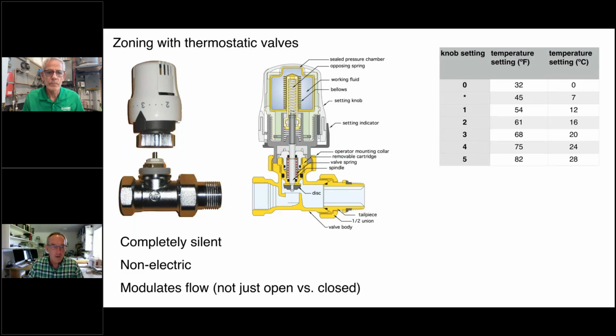So it encourages that. And just to give you an idea, here's what those markings on the actuator or the operator correspond to in temperatures in both Fahrenheit and Celsius over here. And a typical setting is about 3. You see the 3 is lined up here with the indicator. So that would correspond to roughly 68 degrees Fahrenheit. Simple, been around for decades, reliable.